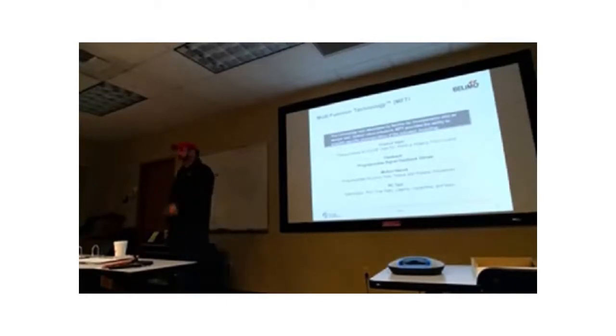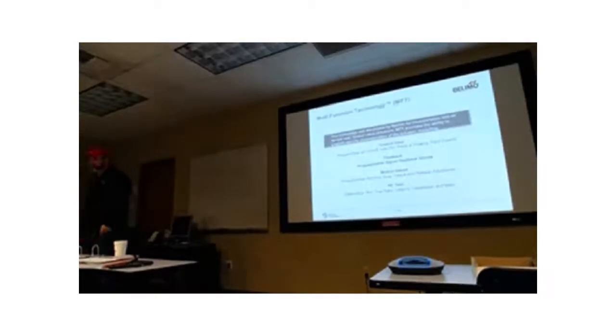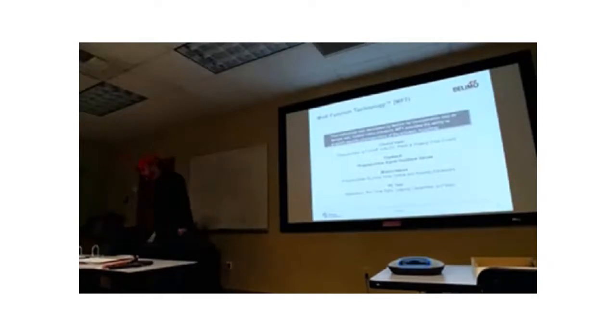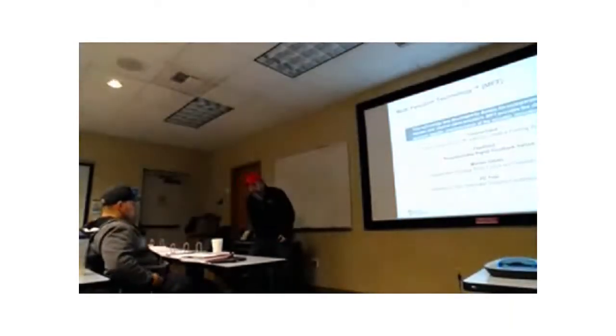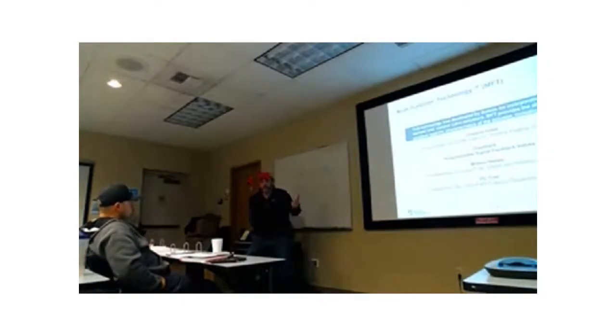Good example, you guys maybe never crossed this. We had a data center where the mechanical contractor decided he would provide dampers that from full open to full closed were 45 degrees stroke angle. Well, the control contractor got on board and said, why aren't they 90 degrees? Well, good news was they got our MFT actuators. They programmed the stroke angle for 45 degrees. Didn't have to buy new actuators, just got the MFTs. So it has some uses.